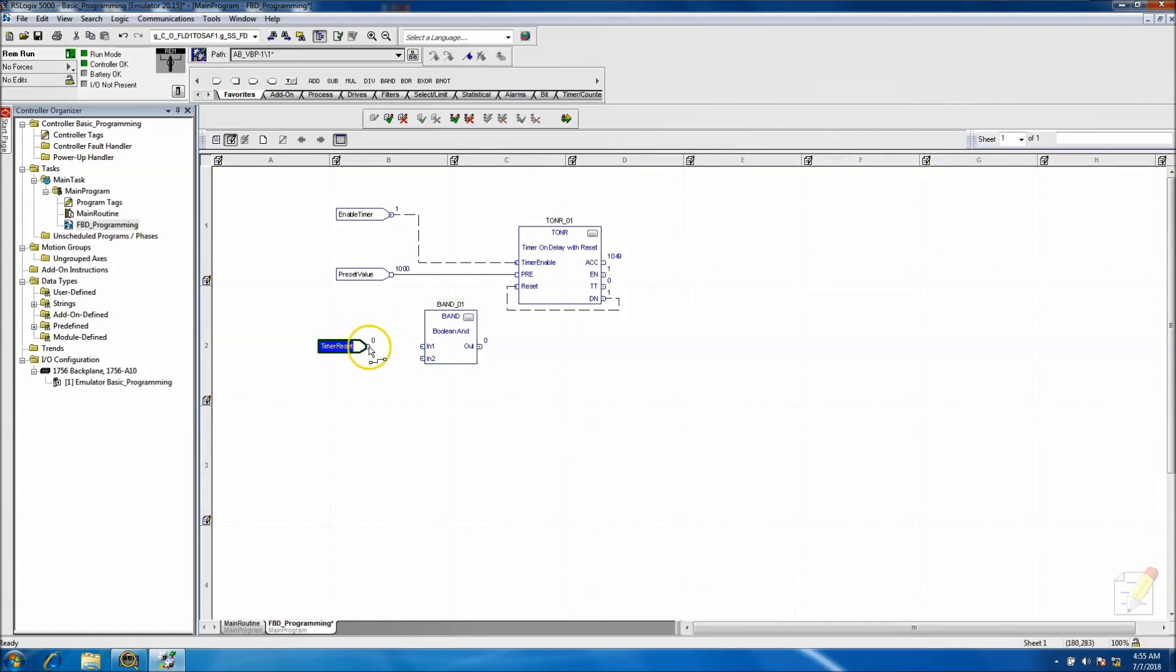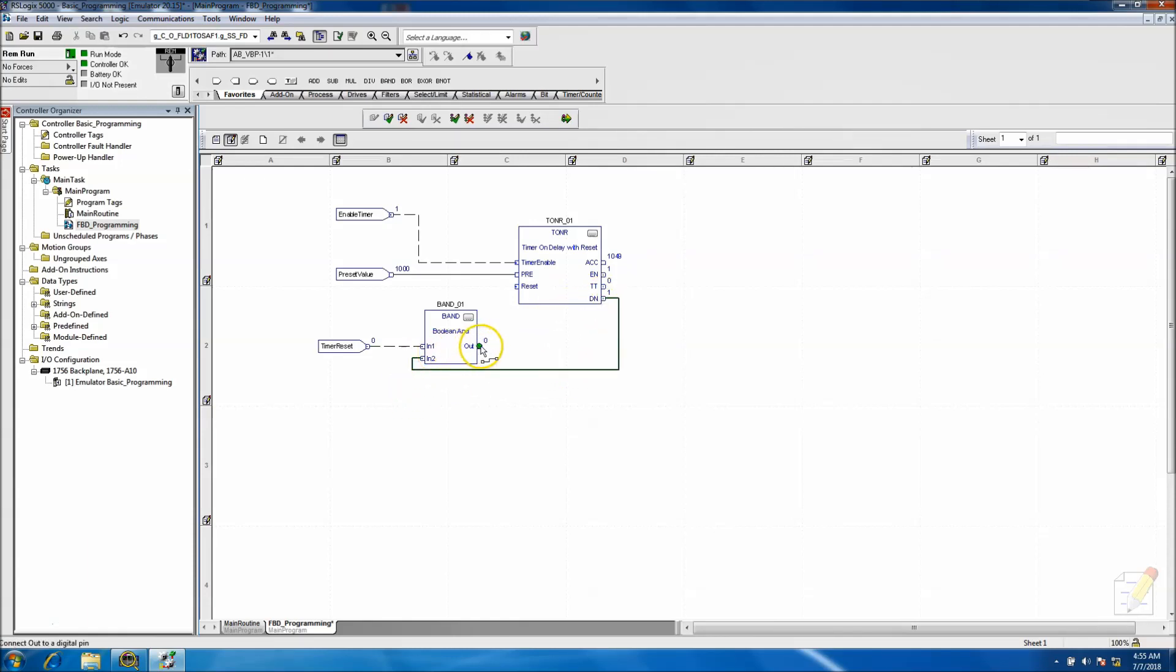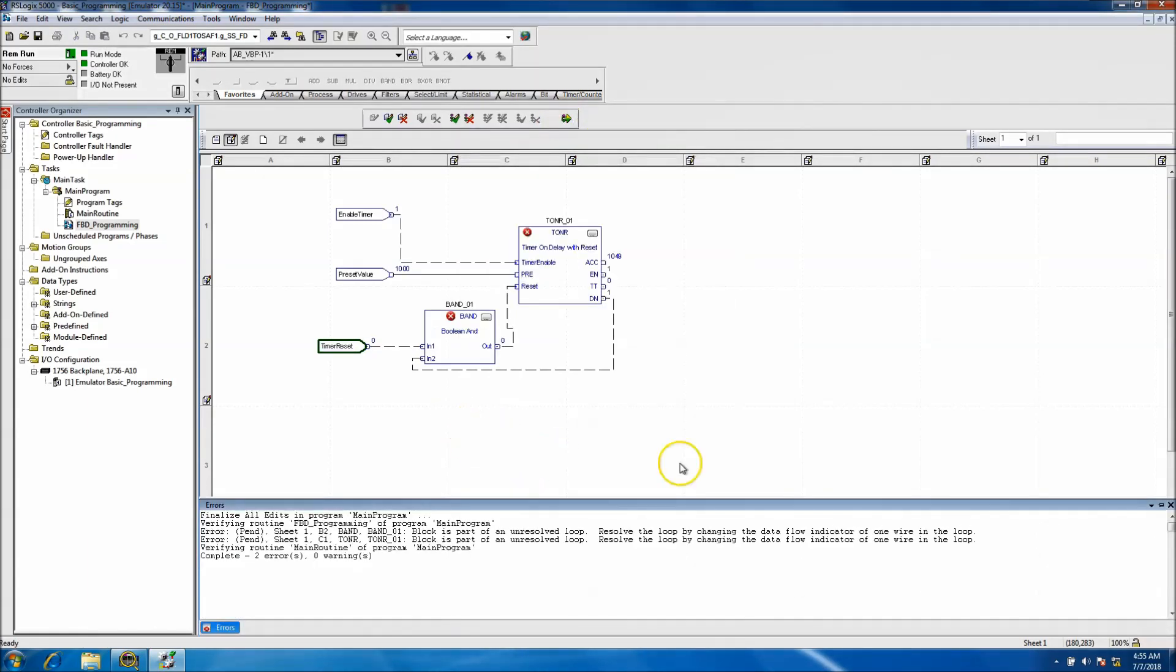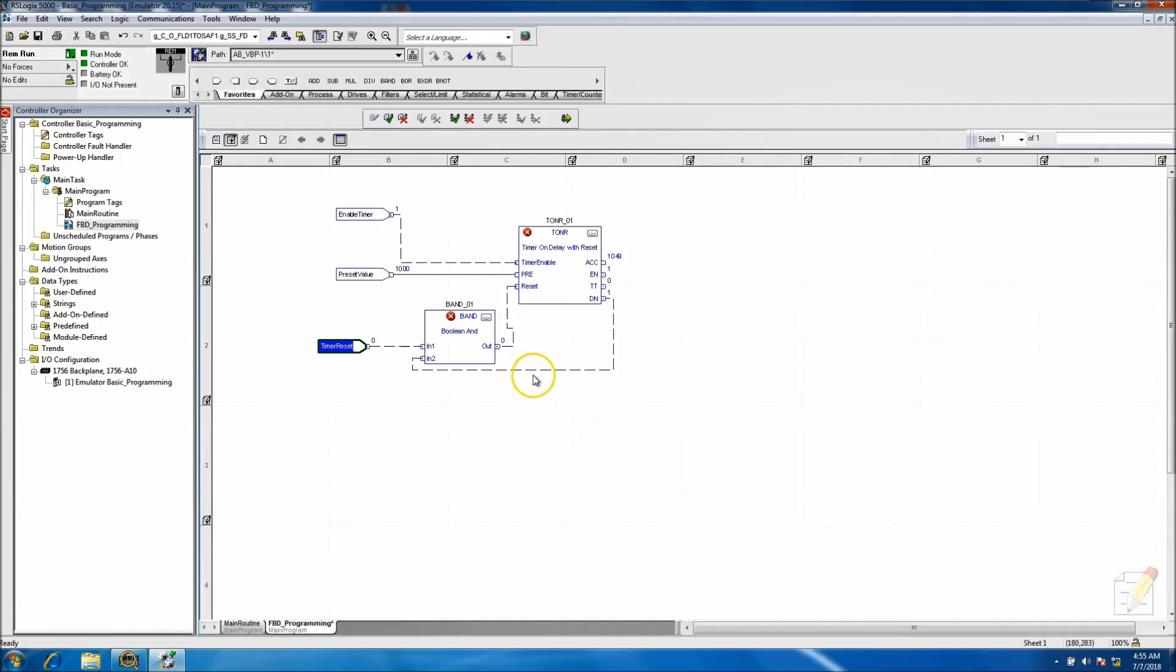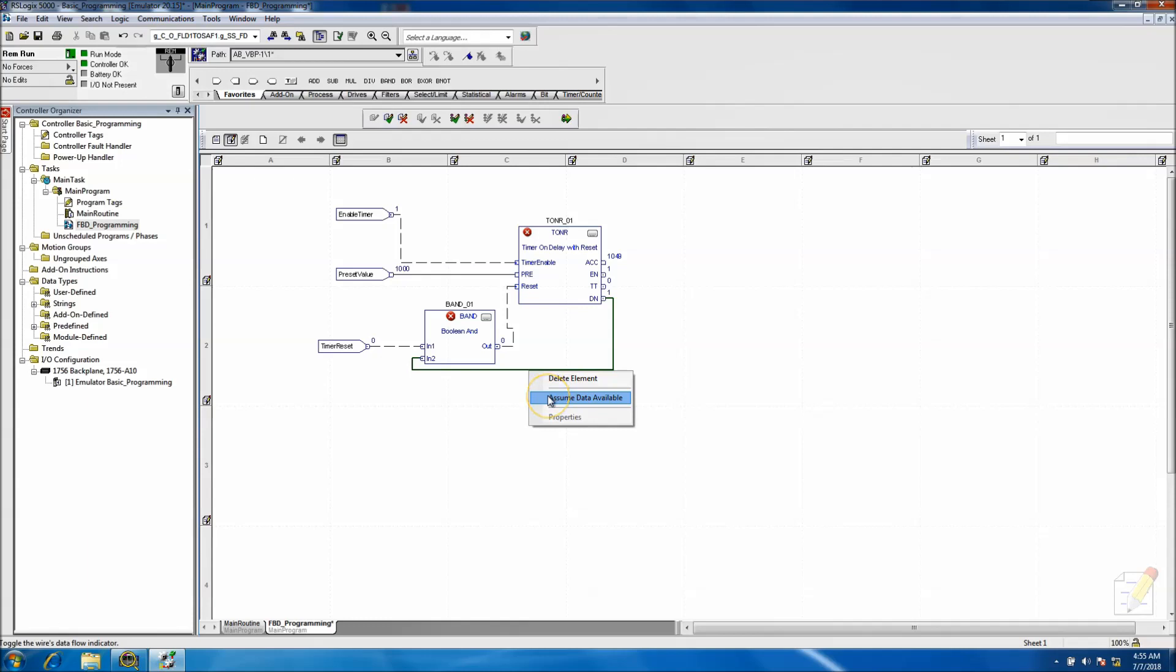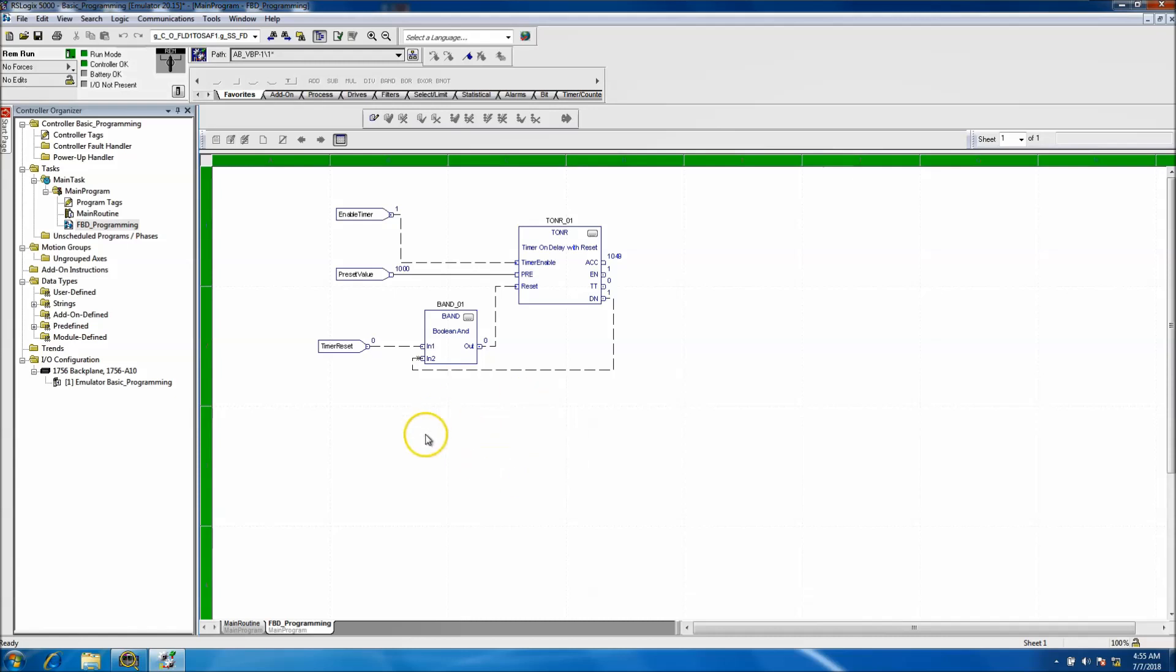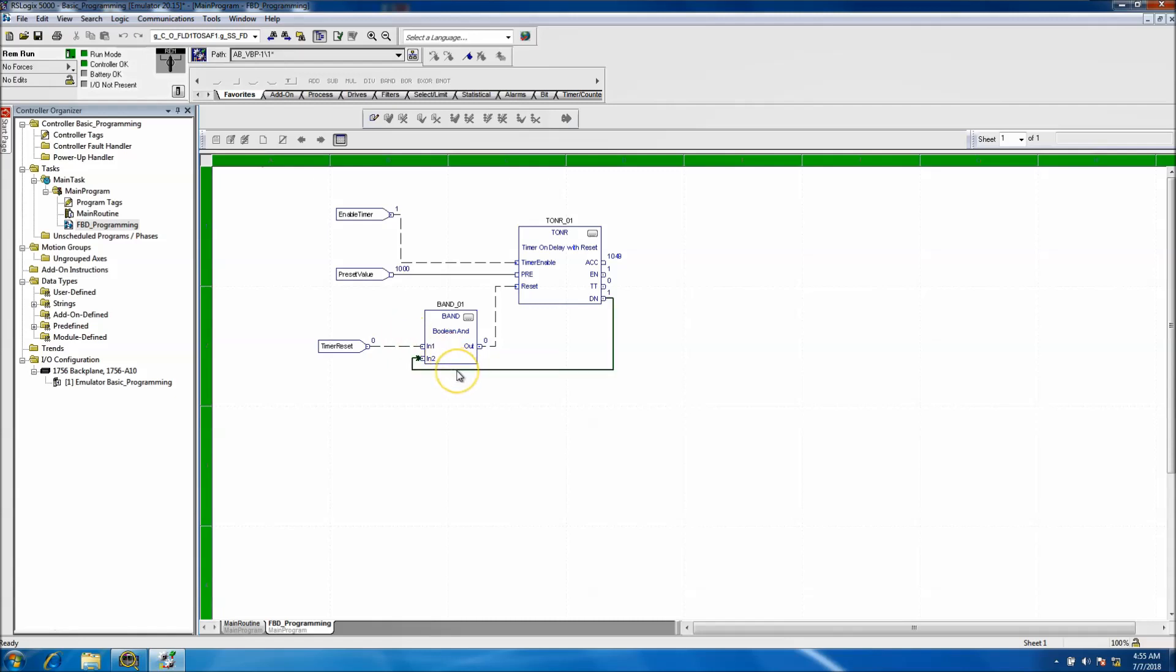And the reset - that the timer reset bit is on - then reset the counter or reset the timer. And so it shows I can't do that. So the reason is because I need to come right here and hit assemble or assume data, and then it should take. So just like that. Sometimes what happens is coming off the back of one instruction to the front of another instruction, you just have to basically make it a known presence where it's at. So that's how you do that. You just right-click and you basically assume the data available.